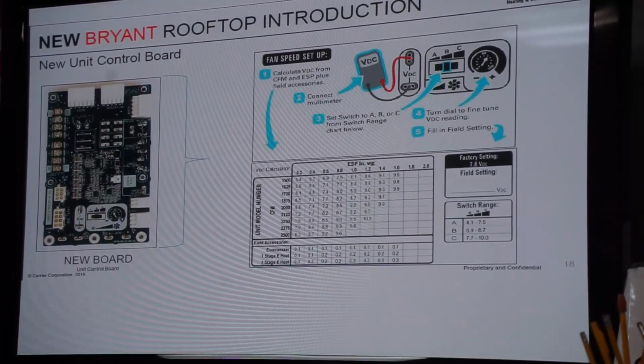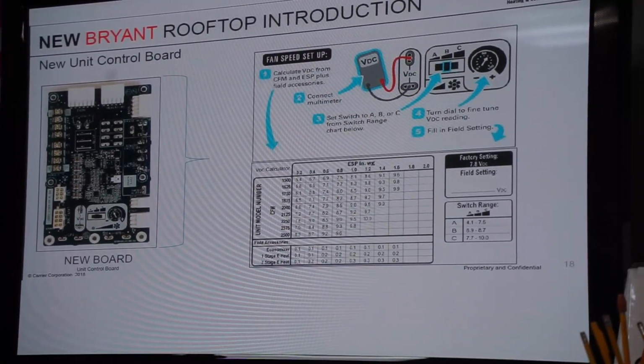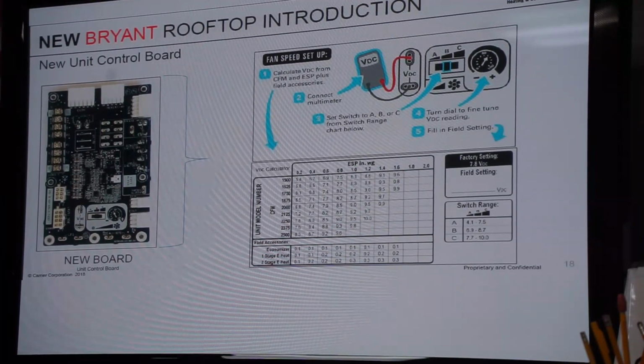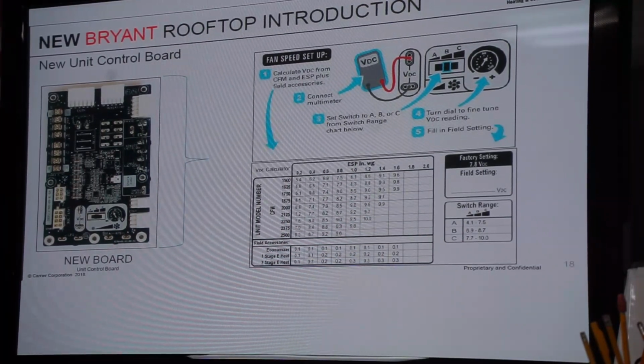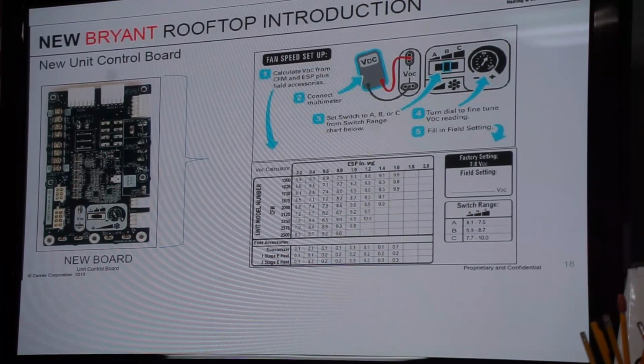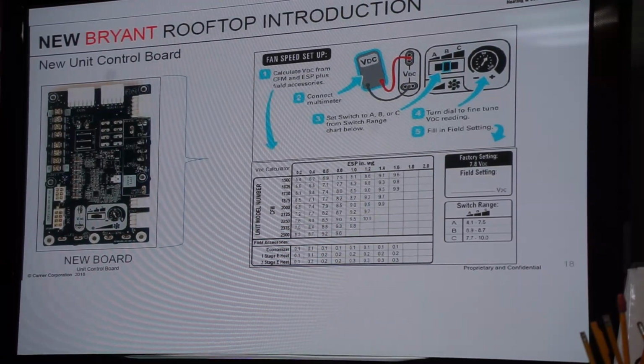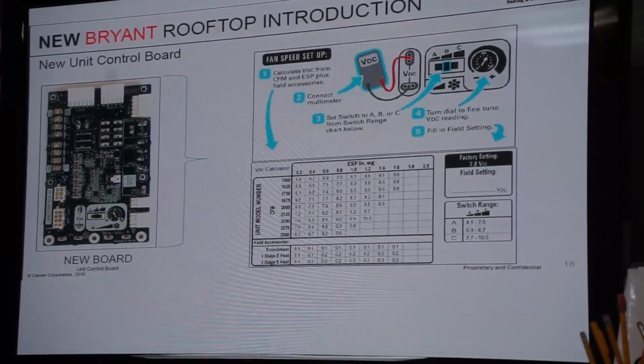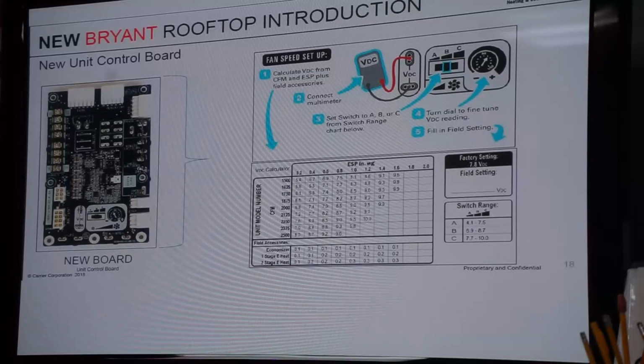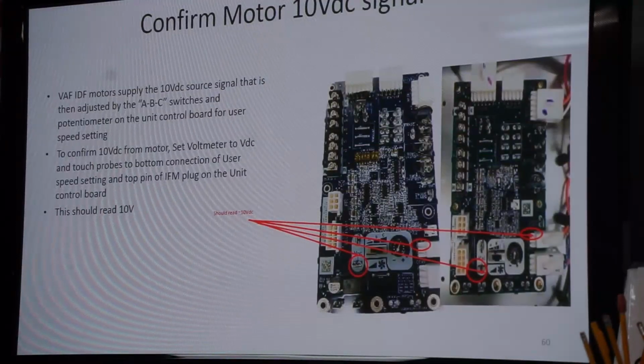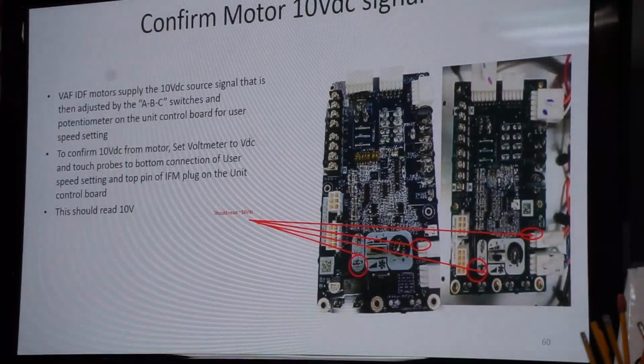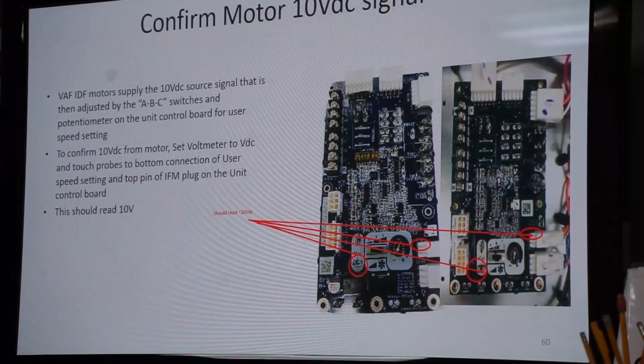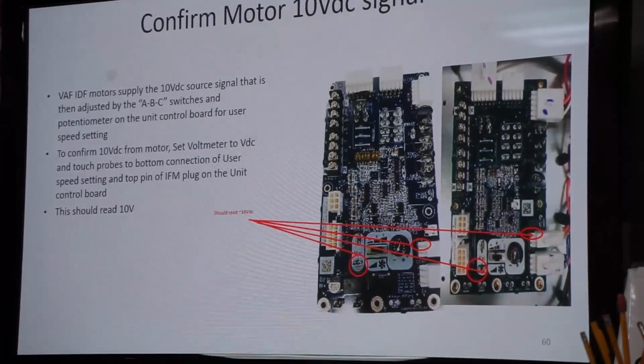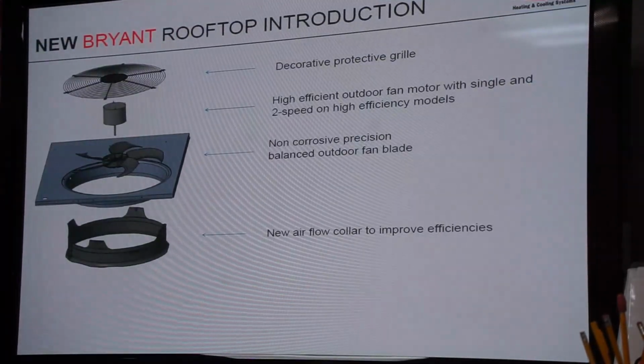That makes sense: how we're getting that voltage and how we're manipulating it and putting it back to the motor. Super simple setup. But again, we're going back to our old school ways of why do we change speed? Why do we have too much air or not enough air is when we're adjusting that. There's those points that we talked about: confirm 10 volts from the motor, ABC selector, condenser fans, ECM as well.